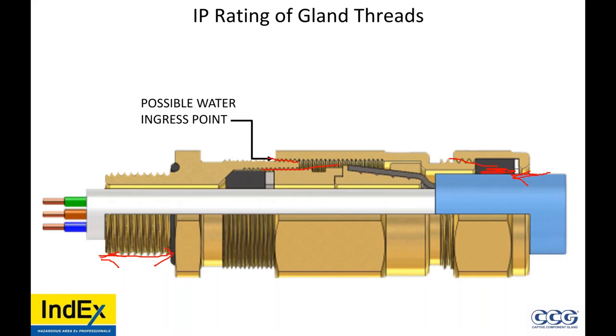So what are the water ingress points? These points I'm showing you here within these threads. Water can get in there, cause corrosion of the armor, and break away the gland. It can also, water goes up cables. It also can go through the gland and up the gland into the device. Water does go uphill. Water does go up. Difference in temperature, pressure. Yeah, water will be drawn up. Do not think that it won't.